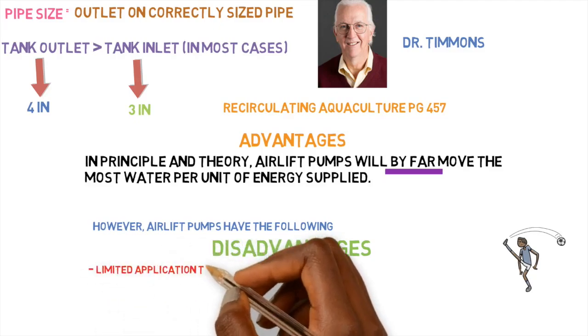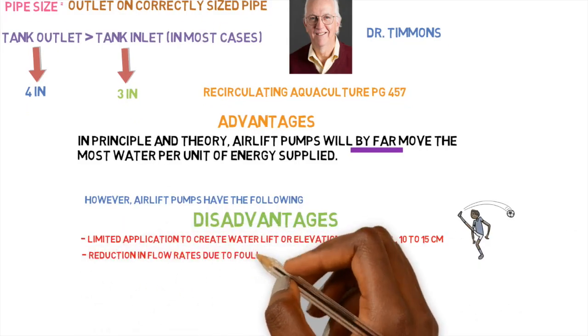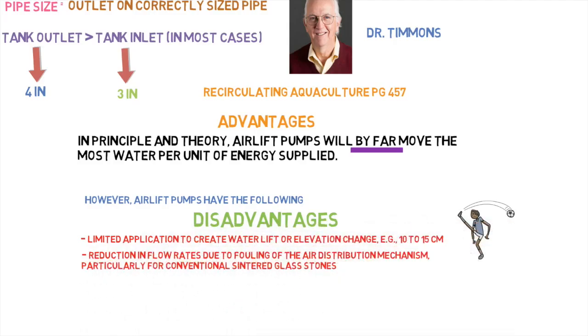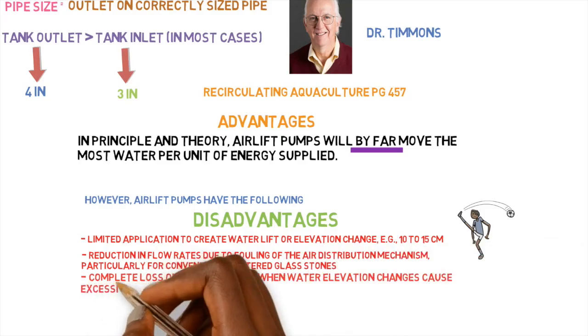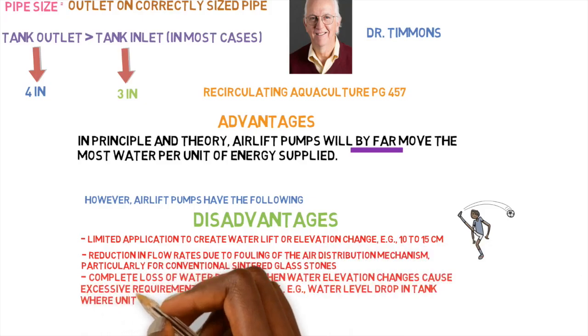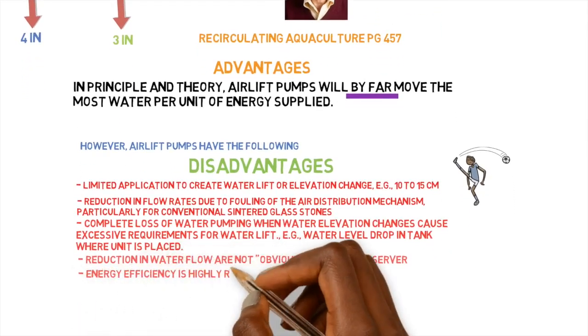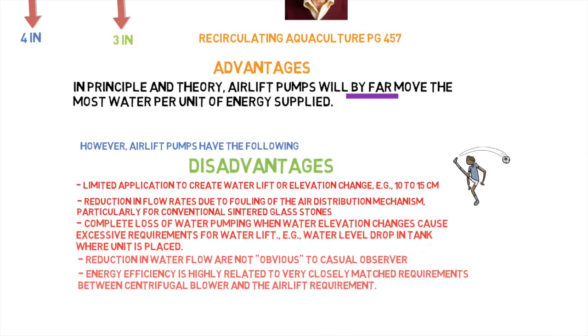So here's the other part of the disadvantages. Limited application to create water lift or elevation change. Reduction in flow rates due to fouling of the air distribution mechanism. Complete loss of water pumping when water elevation changes cause excessive requirements for water lift. Reduction of water flow is not obvious to the casual observer. And energy efficiency is highly related to very closely matched requirements between centrifugal blower and the air lift requirements. So these are the disadvantages named by Timmons.